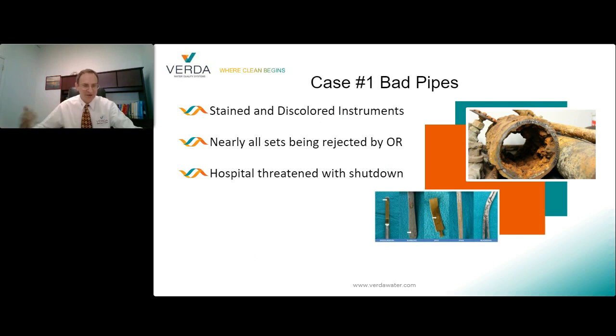The first case is about a rural hospital that had no major issue for decades with the reprocessing of medical devices and instruments. Then something happened: the town experienced a water main break that took the better part of a week to completely fix. The buildup inside the pipes feeding the hospital, accumulated over decades, had started to dry out. When water pressure was restored, the hospital started experiencing discoloration, staining, and spotting because all that gunk started coming down through and into the hospital.